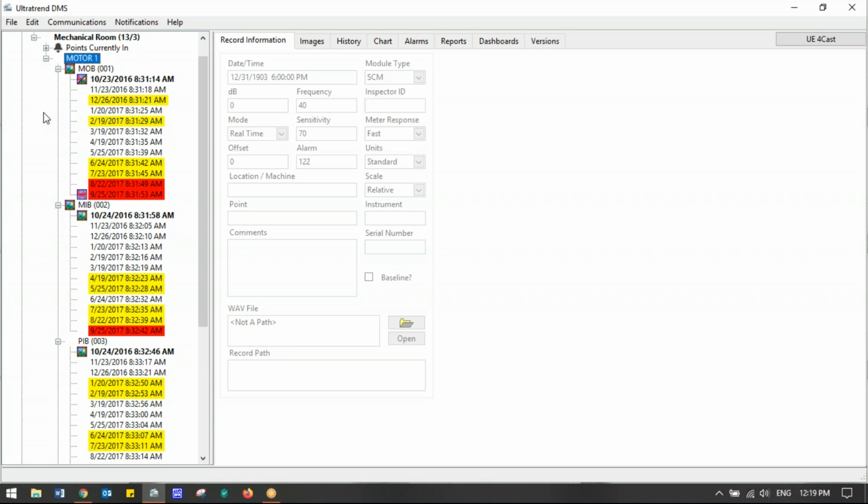When we build these routes, a lot of thought needs to go into building the route and baselining, and that's all the time-consuming effort. Once we get past that, all that hard work, the naming, marking test points, building good routes that are easy to walk, easy for the inspector to take the readings, not going upstairs, downstairs. Get everything on the first floor, then go to the second floor, get everything there, then go to the third floor, get everything there. One side of the conveyor, then the other side, not back and forth. All that kind of stuff. Checking with safety if we need to.